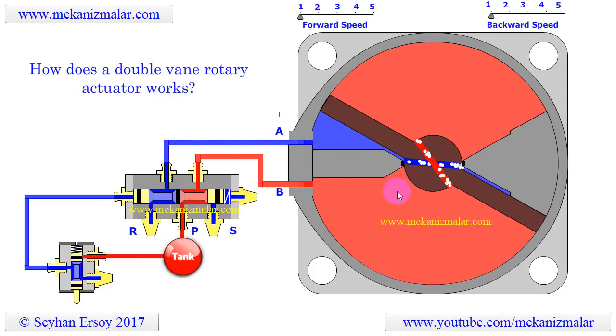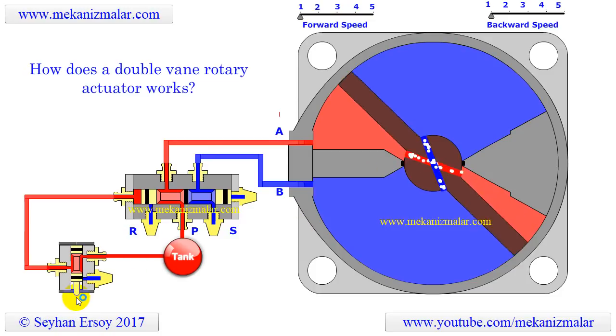The biggest advantage of the double-vane rotary actuator is that its vane is balanced. Since the pressurized oil is acting on two sides of the vane simultaneously, the pressure force acting on the shaft is balanced.